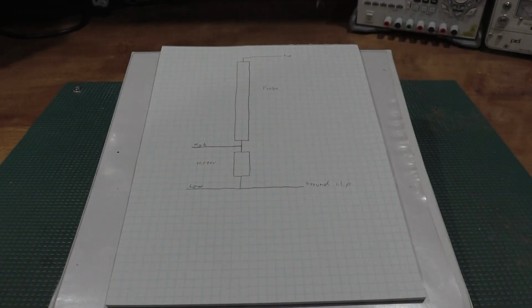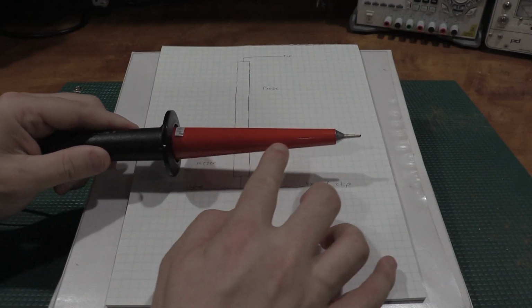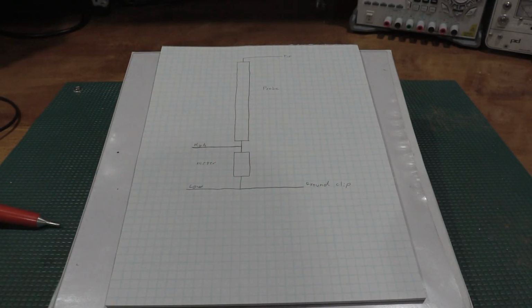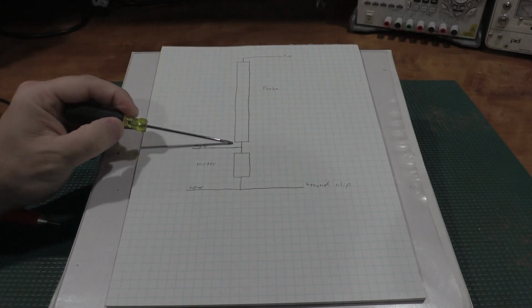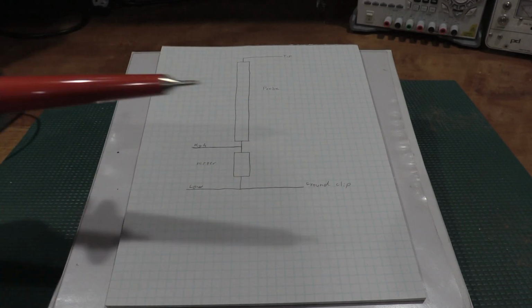Okay, so here's a circuit diagram of what's in the high voltage probe. The way this actually works is the probe sets up a voltage divider with the meter's input impedance to not blow the front end of the meter when high voltages are measured. This part of the probe has a very massive resistor in it. That's all that's in there. Now, I'm touching up here.